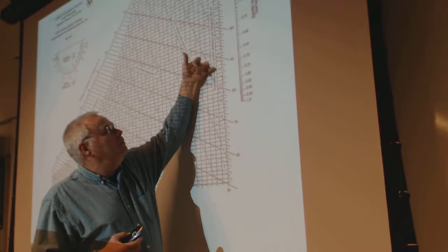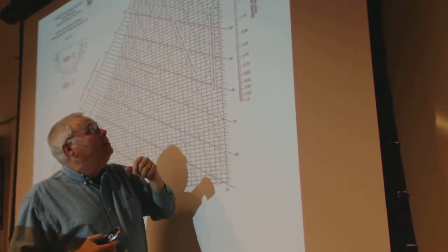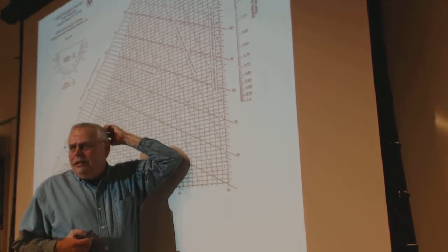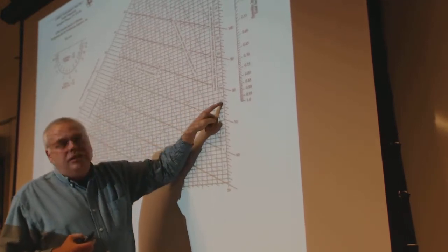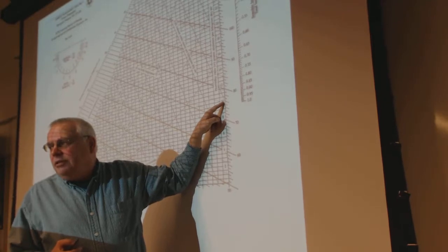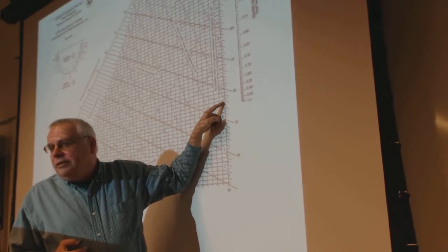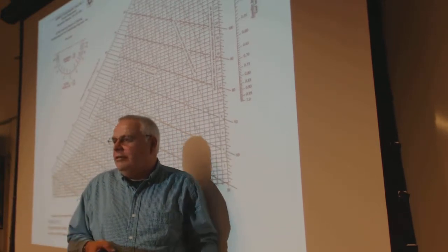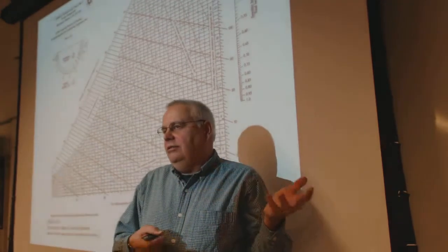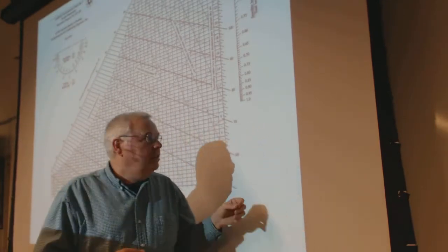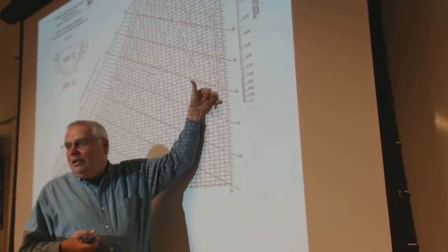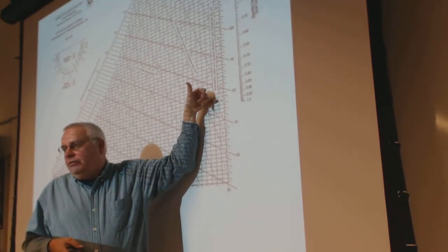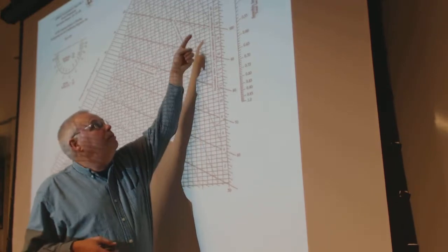And the numbers of 8, 10, 12, 14, 16, 18, up to 30. There's not a lot really in there. If you think about 10 grams per kilogram, what is that in percentage? That's like 1%. 10 out of 1,000 is 1 out of 100. So in this case, 1% of the mass of the air volume is moisture, water vapor. And at 20, it would be 2%.